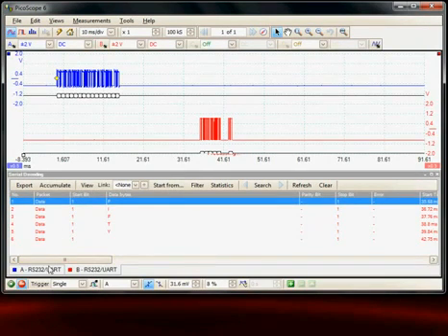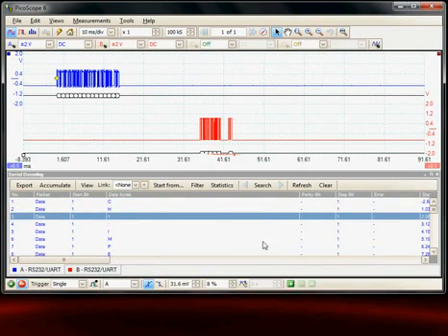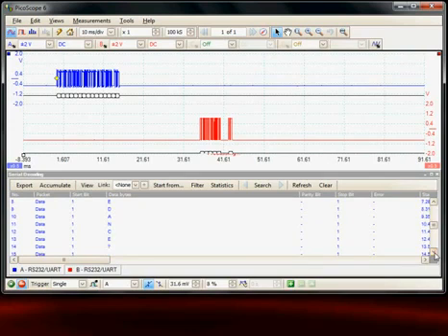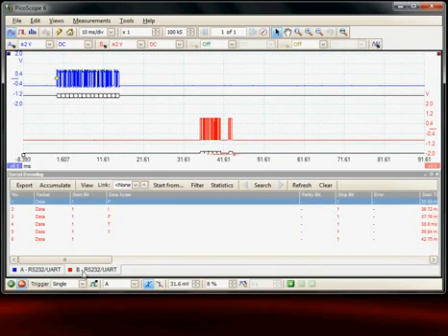Now we can go and have a look at the command. Here we can see the command set out. The command that went out was channel 1 impedance query. So the controller was asking the impedance of the instrument, and then we can see the reply has come back: 50. So it has returned that it's obviously in a 50 ohm format.